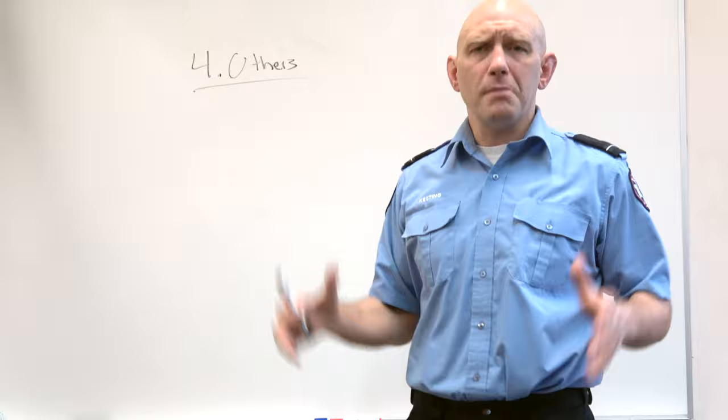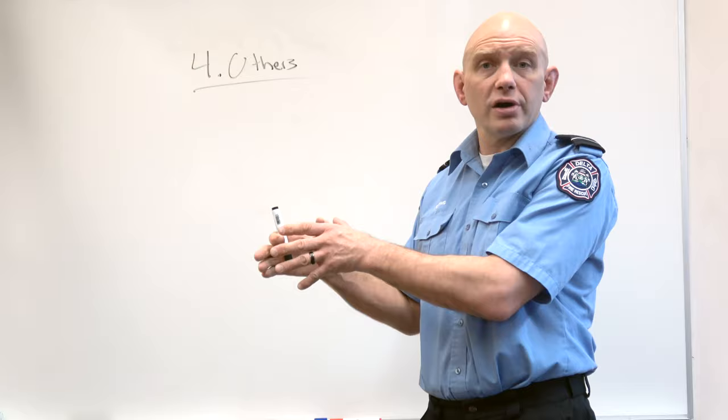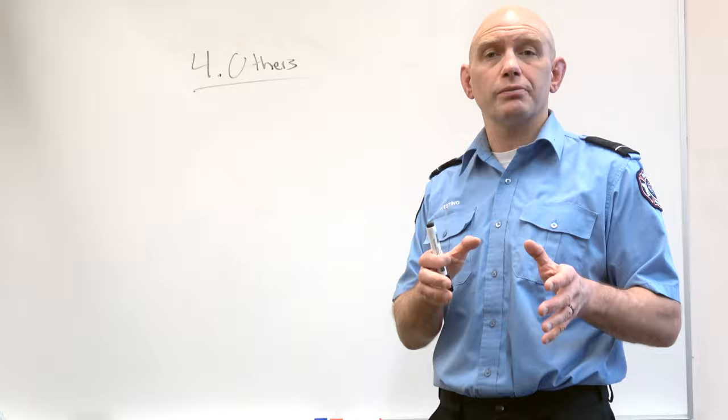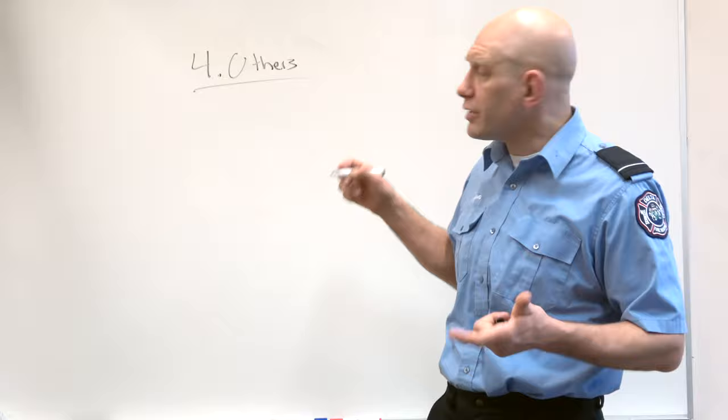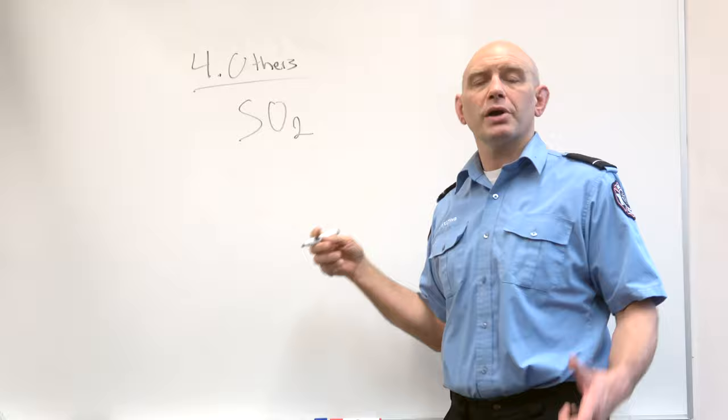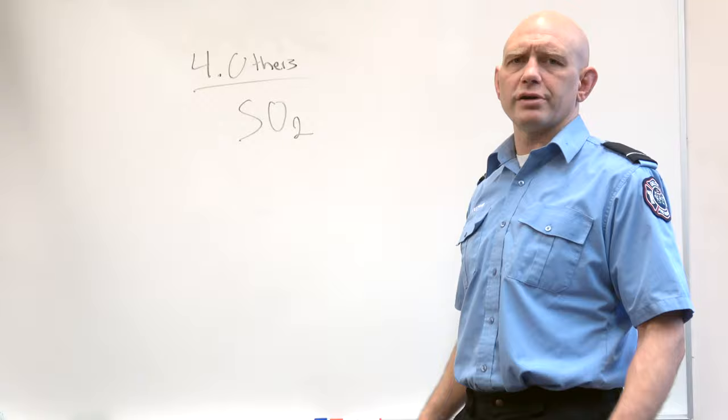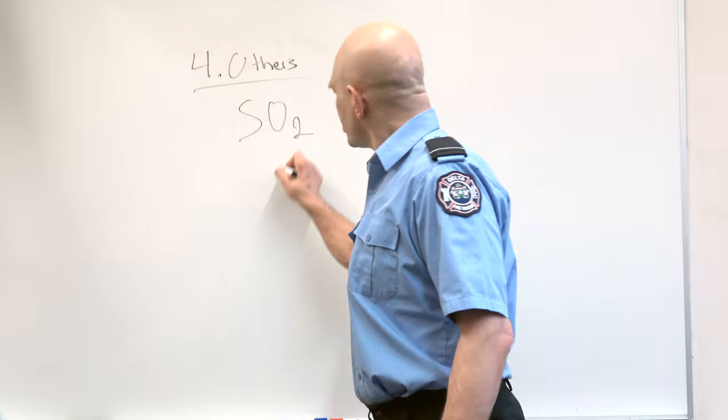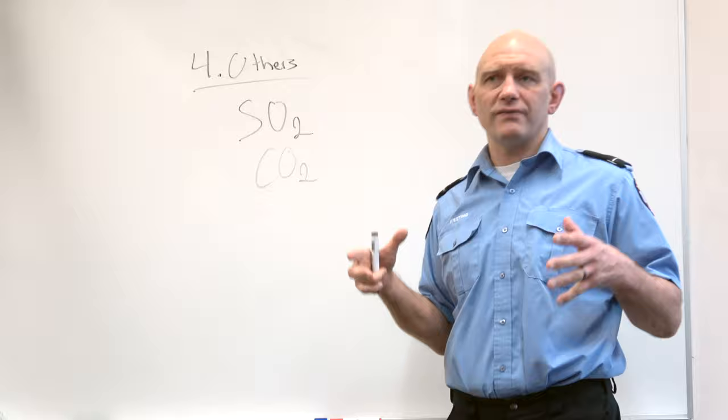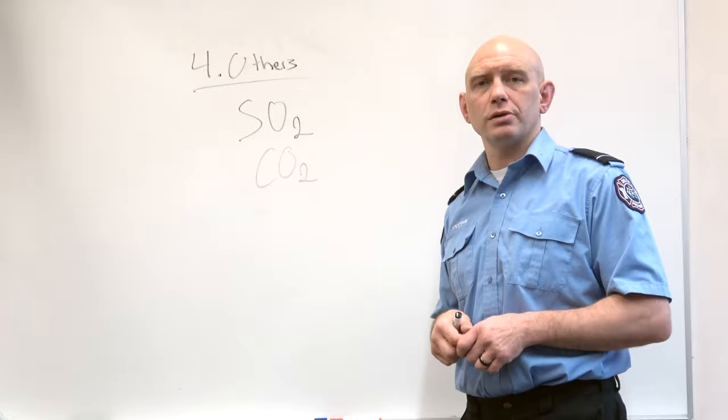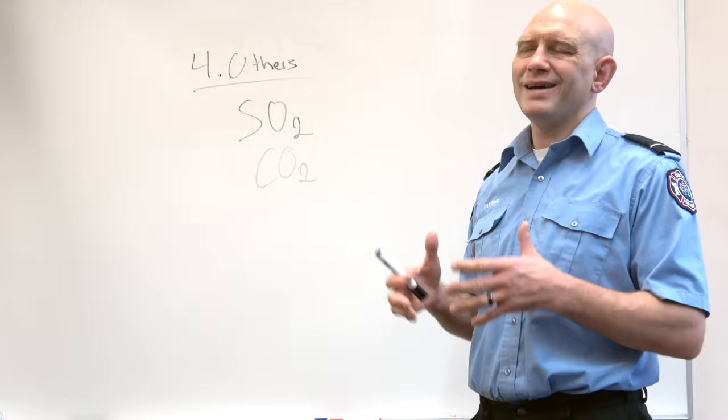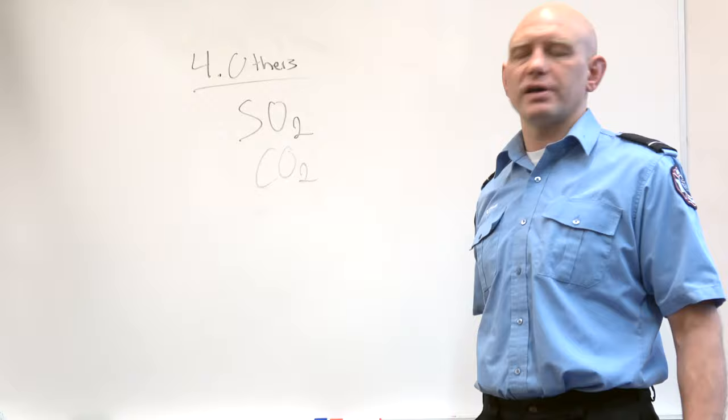Both of these are odorless, invisible, and if you condense them into a liquid, they look like water. In refrigeration systems, as far as I know, it's mostly unodorized, meaning if you have a leak, you're not going to smell it. You've got oxygen displacement problems, obviously you've got flash hazards. Your first line of defense is your LEL meter on your four gas. That's the main way that you can detect this. Incidentally, if you've got a kitchen and you've got a fridge using propane as a refrigerant, they have to make sure that the quantity of propane in that fridge, if it were all to release, is not going to create more than a 20% LEL environment.